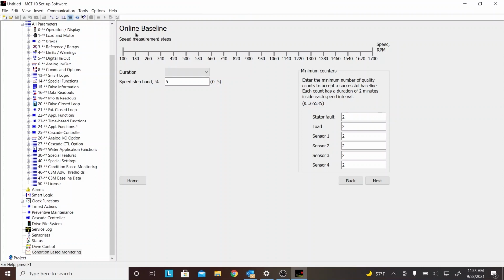Now, online baseline. What that means is we're developing the baseline, all the criteria of that run from 100 to 1700 RPM. We're dividing that into 20 points of information. We're developing that and storing it in the baseline data parameters, and we are doing that over a period of time.